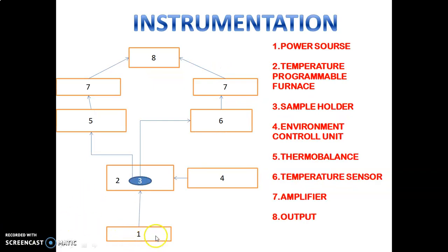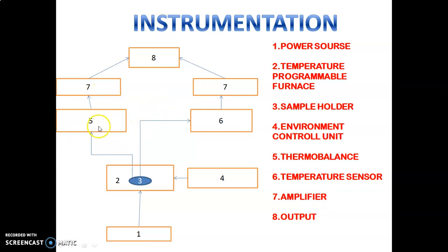There is a power source connected to a temperature programmable furnace. Inside that there is a sample holder in which we place the sample. The environment controller unit provides a suitable environment for the analysis. When power is supplied, the instrument heats according to the given program. The temperature sensor measures temperature regularly, while the thermo balance measures the weight or mass of the substance. Both data are given to the amplifier, which produces the output known as a thermogram.